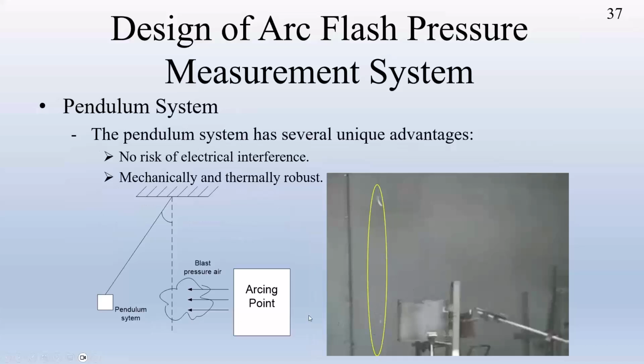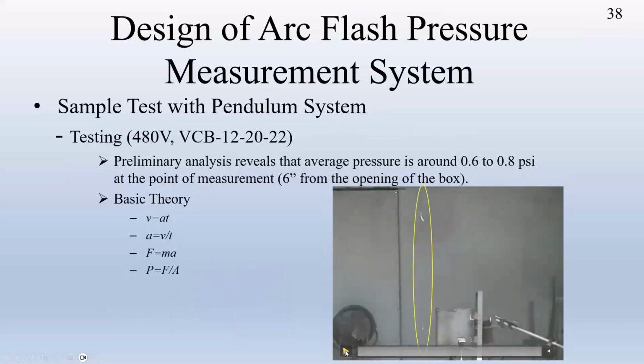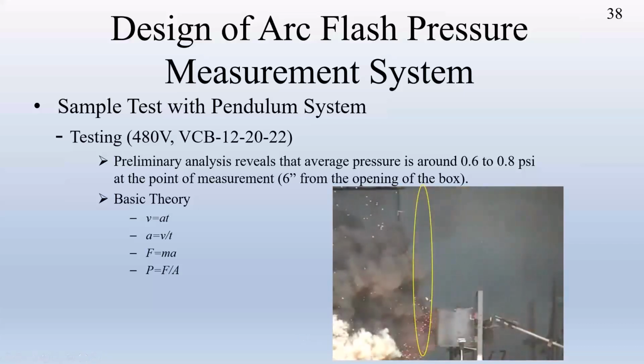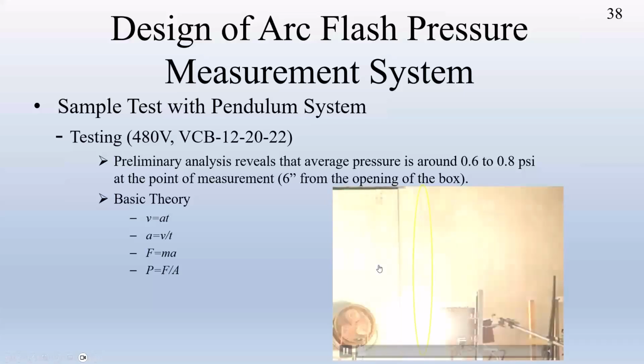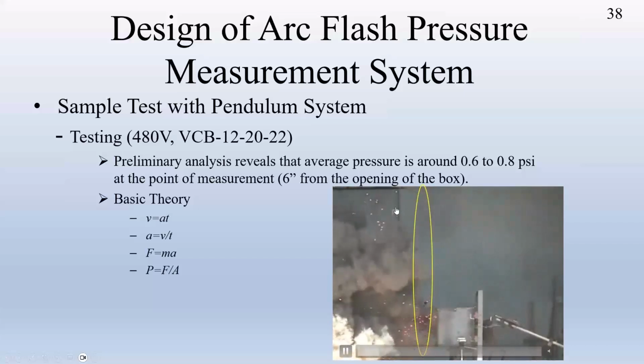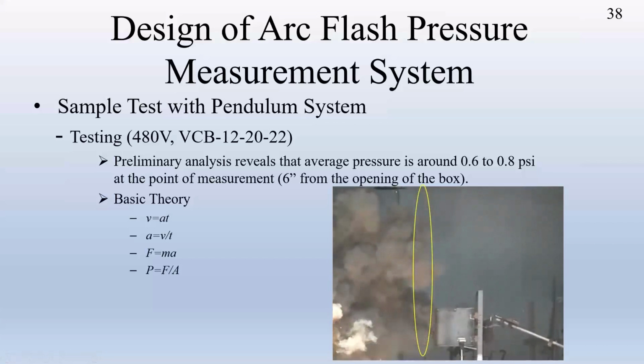Then I came up with the idea, okay, well, let's use a pendulum here. You can see here, I have a pendulum, and I know during the arc it's going to have a lot of smoke, so I tie a knot here, and this is the metal plate. So when you have a metal plate over there, they push it over, so you can see here, and then during the arc, here you can see how they move. So on that way I know how far the pendulum moves, and then what is the speed, and then we can basically calculate what is the pressure. And in this particular case, we have about 0.6 to 0.8 psi.